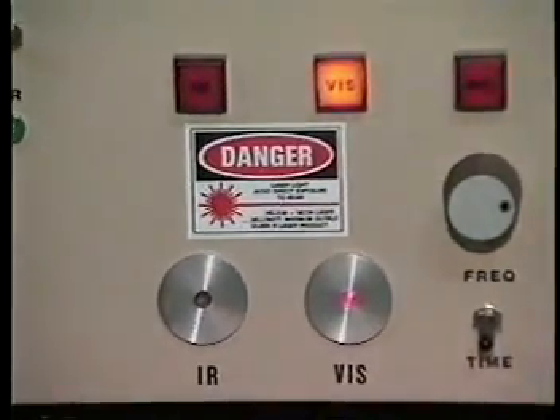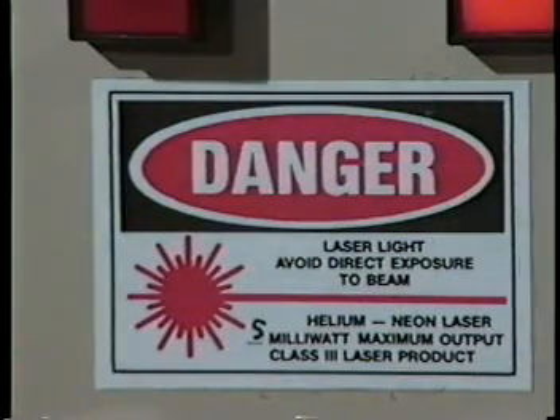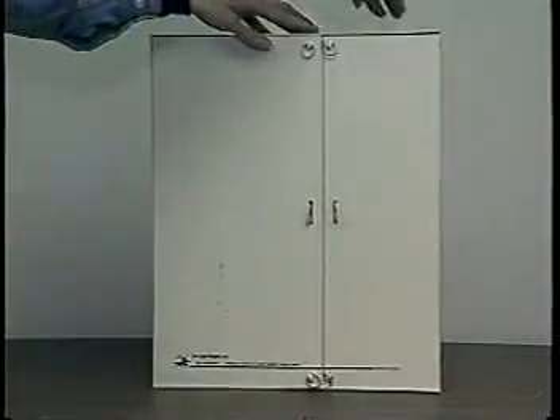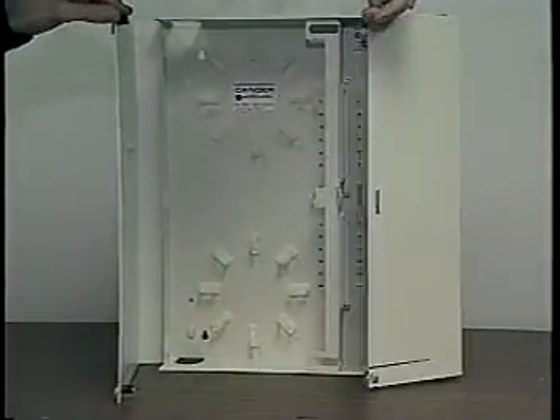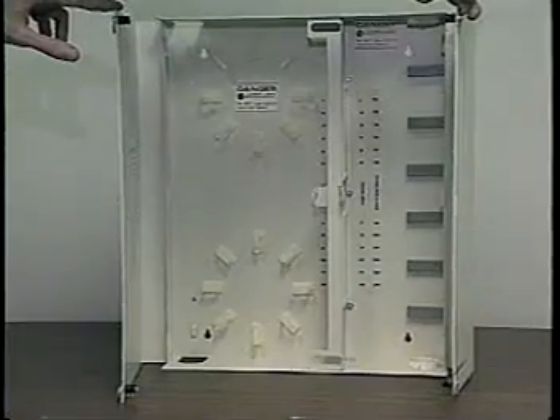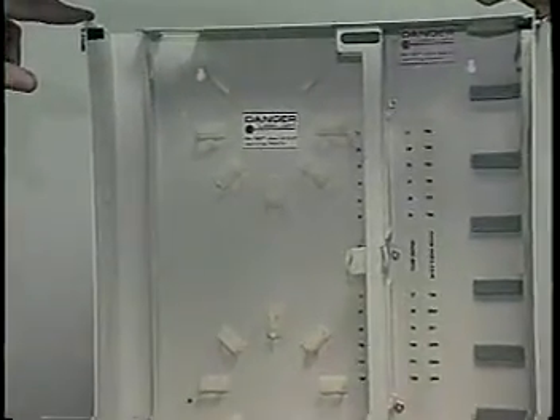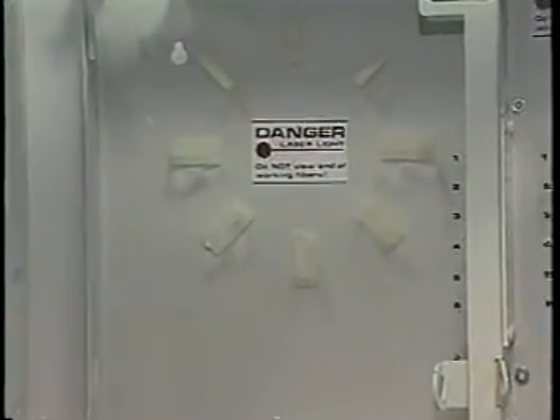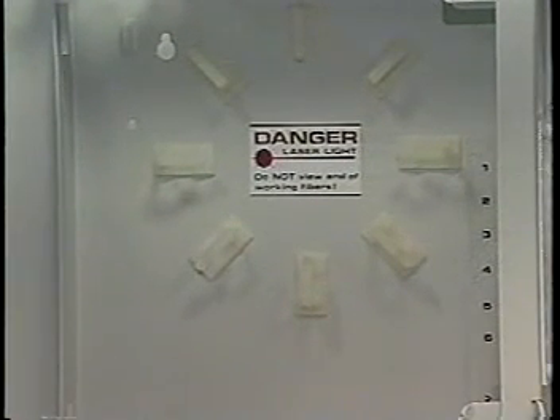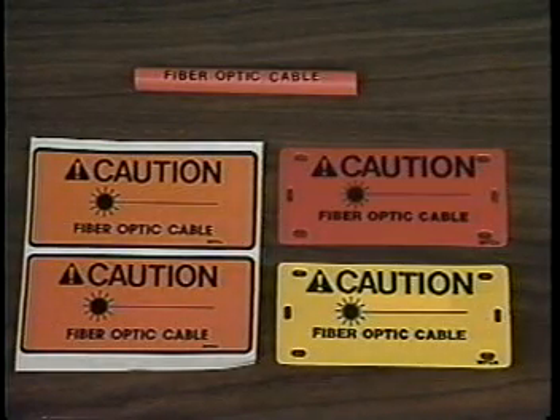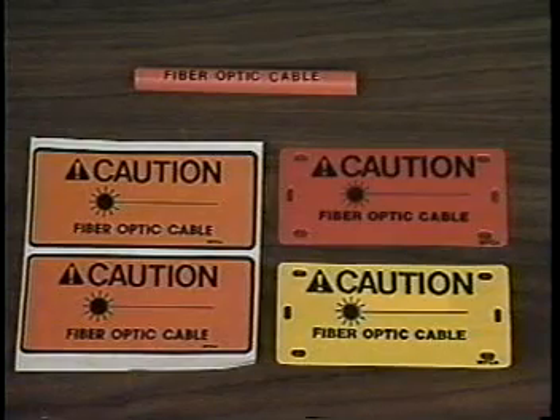The label must state the type of laser, its class as well as precautions, and a brief warning message as to the type of danger the laser presents. Since patch panel manufacturers do not know what types of light sources will be cross-connected at the panel locations, many provide safety labels already on their products. Since the actual laser type may be unknown to the supplier, these labels may not supply the proper information for adequate safety guidelines. Safety labels may be purchased through many suppliers to meet actual performance specifications.